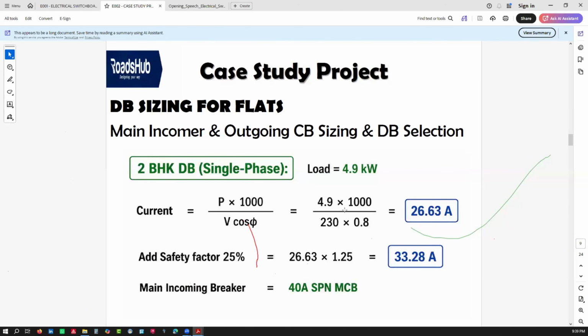Now, you've done load estimation, you've done transformer sizing, and you need to know what your dB sizing is for each room. So we've said we have 2 bedrooms and 3 bedrooms. For the 2 bedrooms, you need to get the breaker that is required for the incomer. You know, distribution boards, everyone knows dBs. And I've also told you, since this is a load that is below 5 kilowatt, you cannot use a three-phase dB. You will use a single-phase dB. And that's just a rule of thumb.